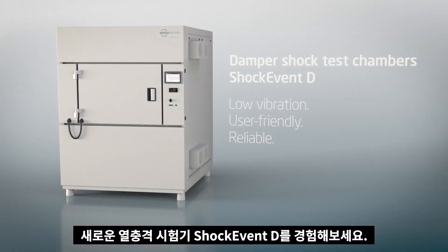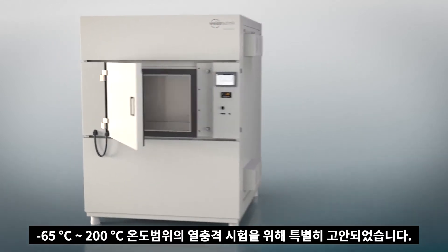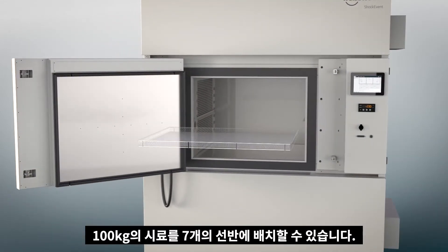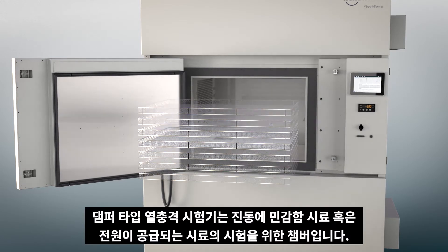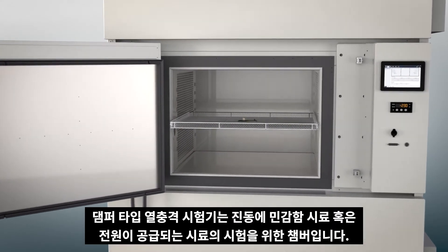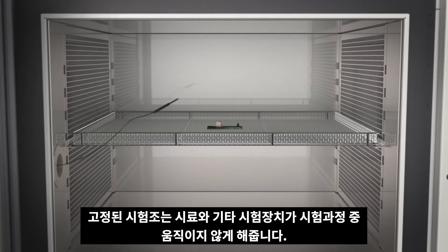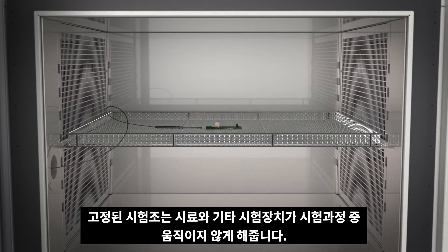Experience the new ShockEvent D temperature shock test chamber, specially conceived for a temperature shock range between minus 65 and 200 degrees Celsius. A 100 kilogram test load can be distributed over seven insert grids. The test chamber is predestined for test specimens which are sensitive to vibrations or when energized.